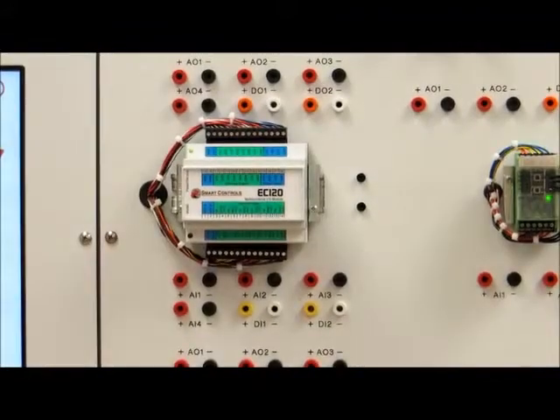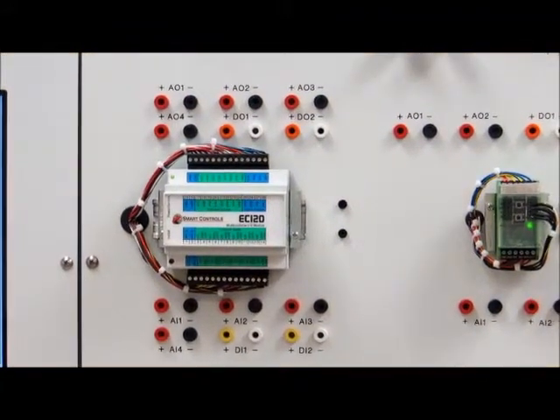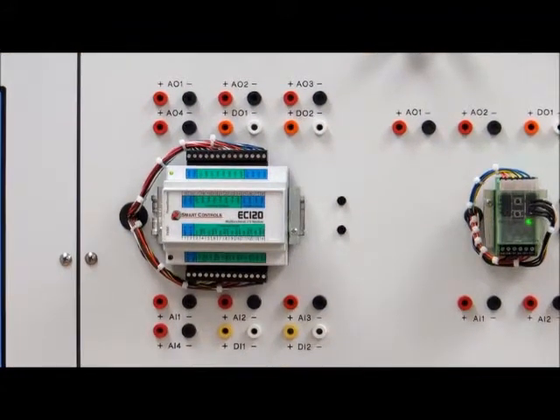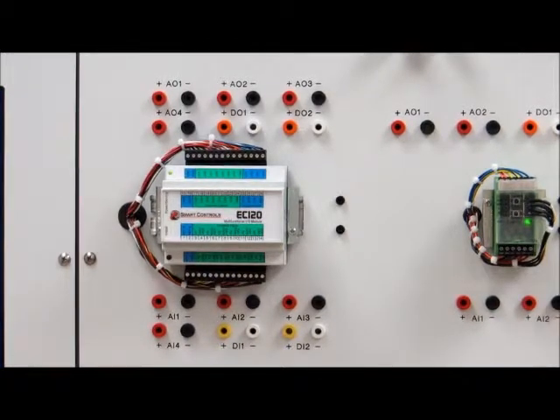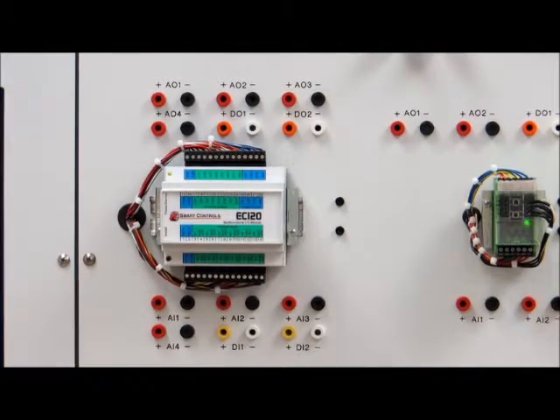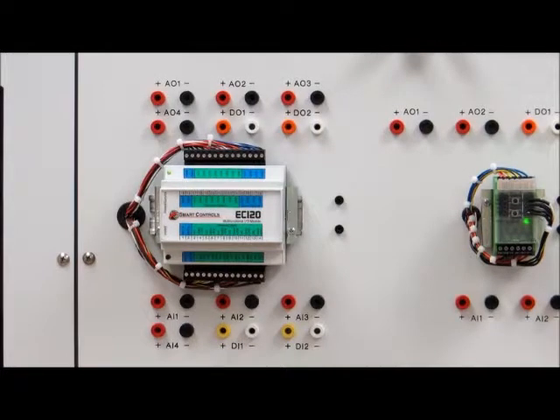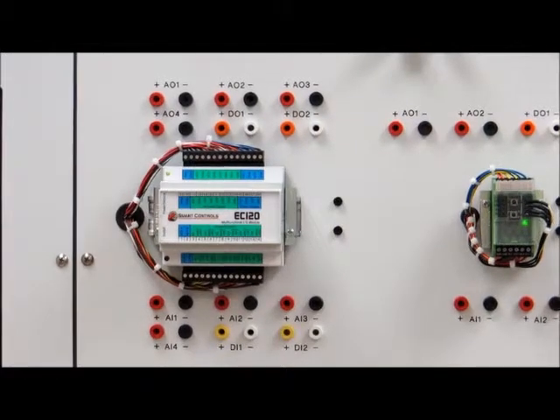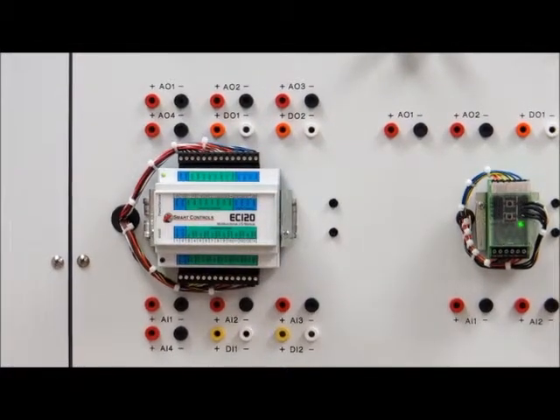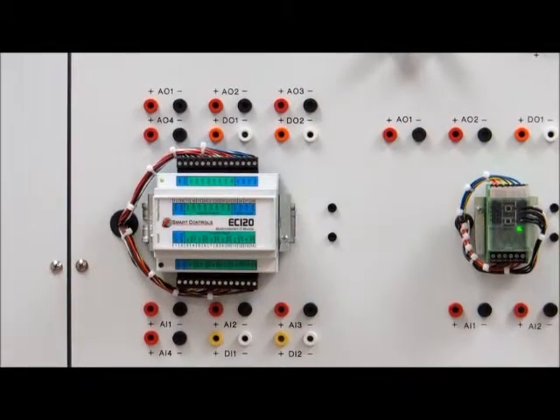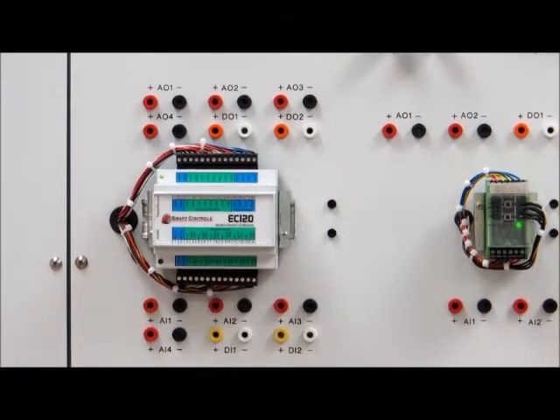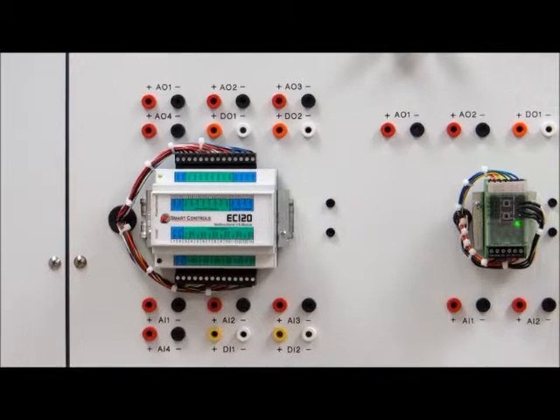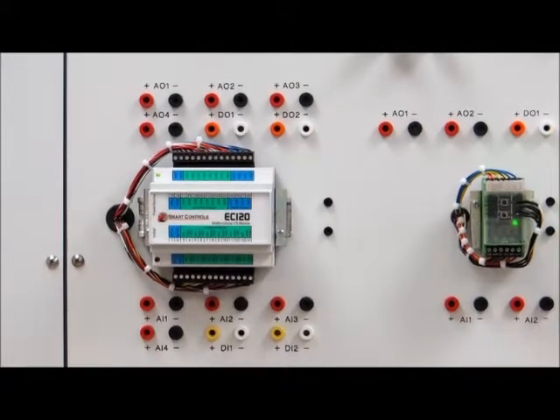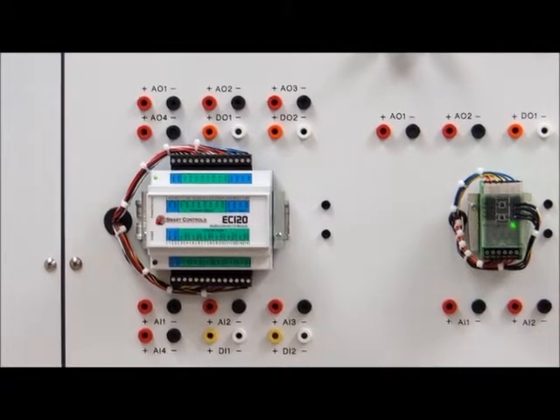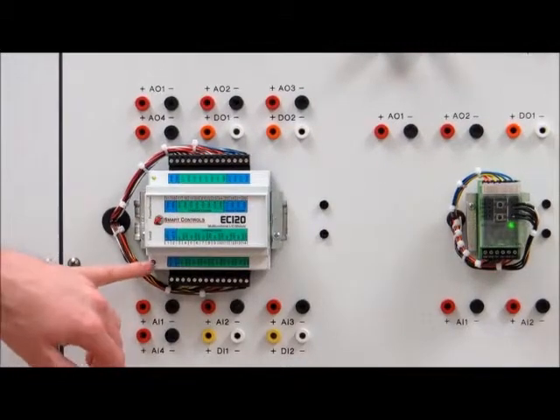This is the Smart Controls analog input-output module. There are 2 devices like this on the trainer. This is module number 1. The module has 4 analog outputs and 2 digital outputs, and 4 analog inputs and 2 digital inputs. The analog outputs are 0 to 10 volts, and the analog inputs are also 0 to 10 volts. This device does talk over the network, and the service pin for this device is in the bottom left-hand corner.